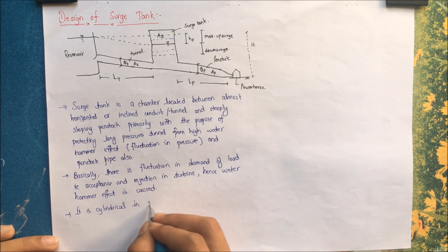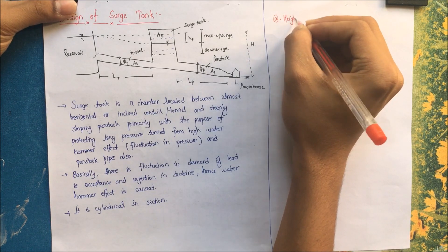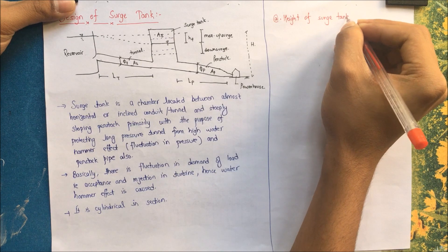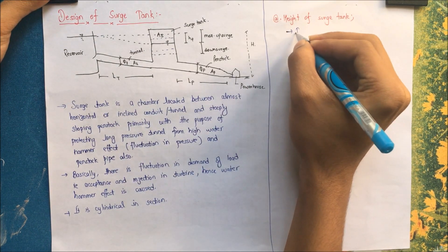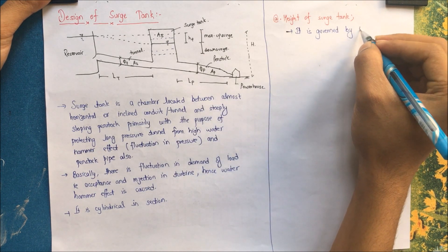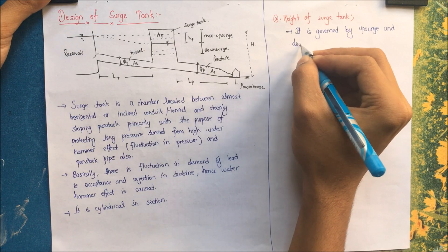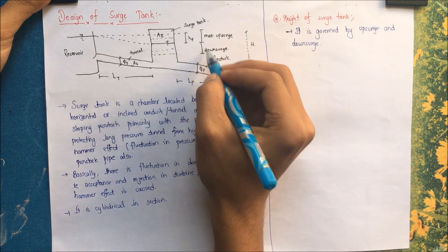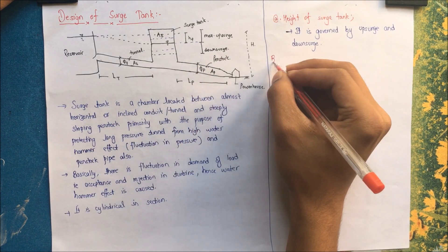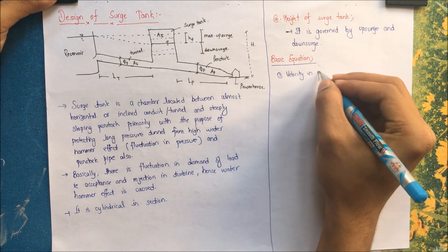Now let us go to the design process. First, the height of the surge tank is governed by the upsurge and downsurge — that is, the fluctuation of water in the surge tank — which also depends upon the fluctuation of load. The basic formula we have to consider first is the velocity in the penstock.